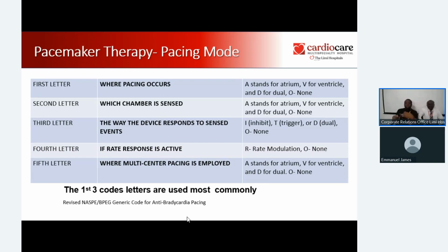Number one, we need to know where it is pacing, whether it is pacing atrium and ventricle, and that is the first letter. So when you hear a pacemaker described as DDD, the first D means it is pacing both atrium and ventricle. The second D means it is sensing, so it will sense what is happening in the atrium and ventricle. And the third letter will tell you whether, if it senses something, it should trigger the pacemaker, inhibit it, or do both, depending on your setting, or do nothing at all.